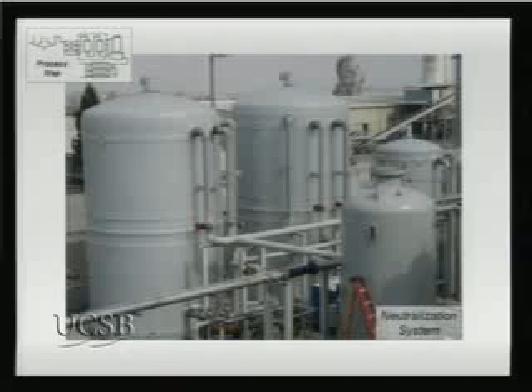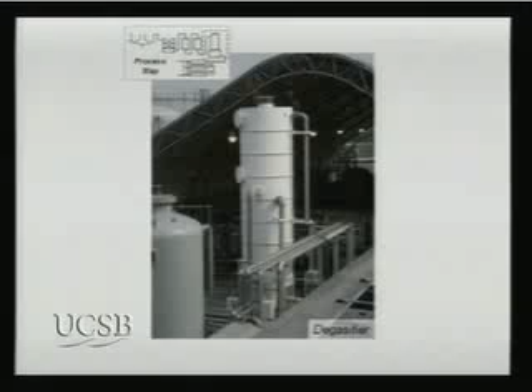These remove that, and then we go through the neutralization system for the WAC ion, since it's an acidic process, through the decarbonator tower. This takes the CO2 out. Once the CO2 is out, we blow air through the bottom. You've got this really carbonaceous water, it falls through the packing and mixes with the air, and the CO2 comes off and just wants to leave. Once the CO2 is out, we jack the pH up to about 10 to 10.5, so you've got to have no hardness present whatsoever, because there's still some silica in this water, and that creates some big problems.